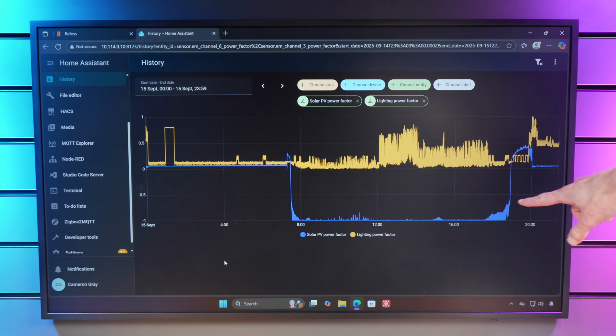Then over towards the right hand side, you can see the power factor for the solar circuit started increasing again. That's when the solar would have stopped generating. There's a period there where it almost went above 1. That's probably some sort of self-consumption of the inverter. Then it flattened down and went back to very close to 0 again. And once again, once it's very close to 0, the lighting power factor is now higher because there's currently lights on. There wasn't lights on over here.